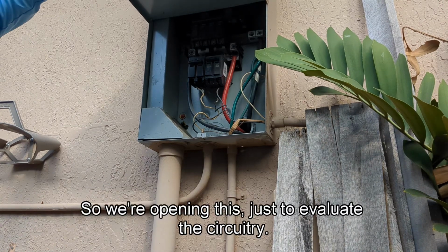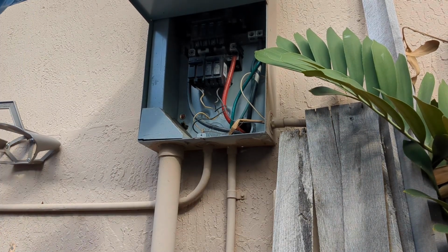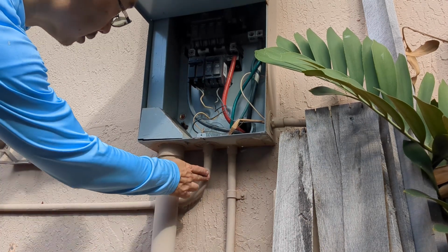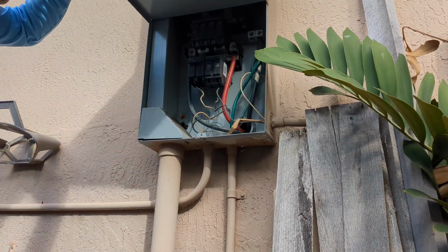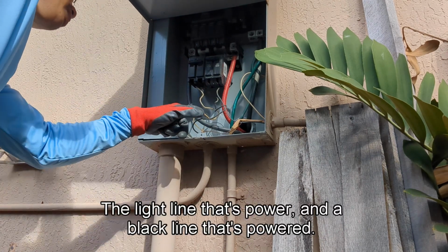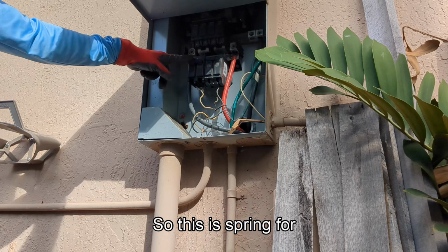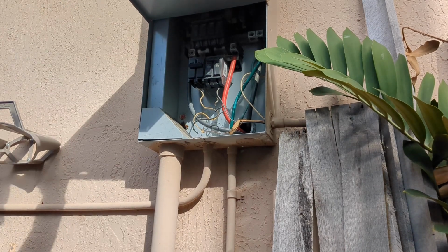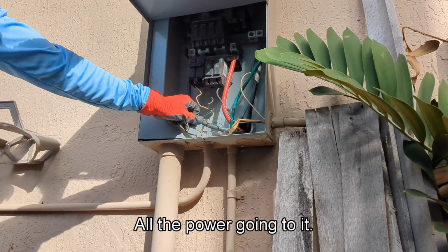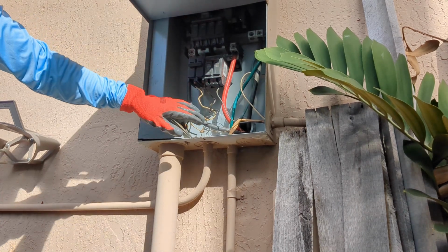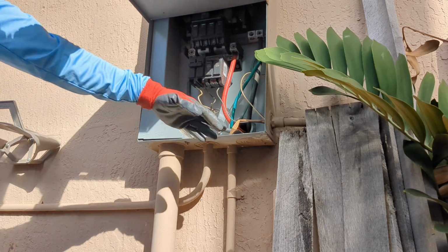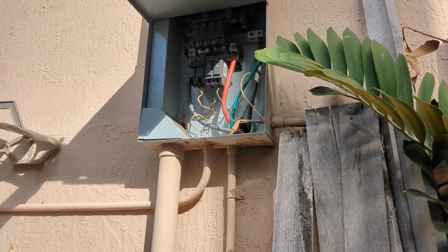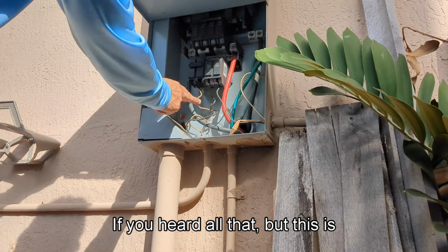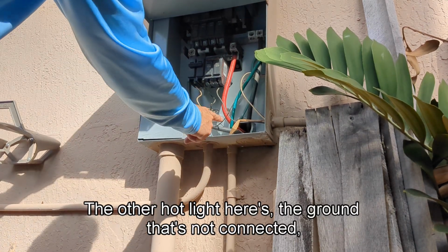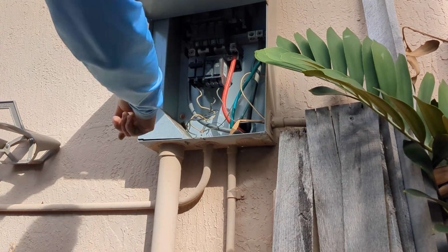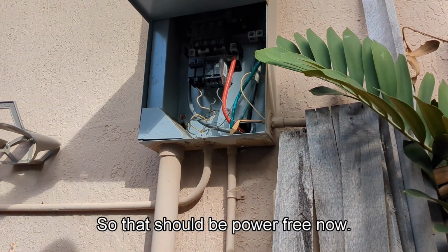So we're opening this just to evaluate the circuitry. So the line goes from here. We have a white line that's power and a black line that's power. So this is the sprinkler. It should kill all the power going to it. And 220, ground is not connected. We'll fix that when we're done. I don't know if you heard all that, but this is one hot leg, the other hot leg, because the ground is not connected. We'll fix it when we're tidying things up. So that should be power free now.